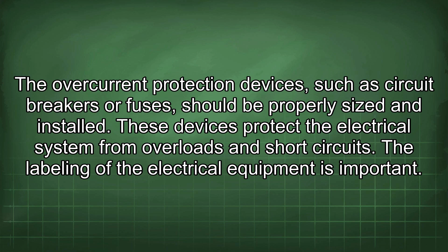The labeling of the electrical equipment is important. All electrical equipment, including meter centers, disconnects, and electrical panels should be properly labeled with clear and concise information. This helps ensure safety and facilitates maintenance and repairs. Consider future expansion when planning the electrical service. If there is a possibility of future expansion or increased electrical load, it is important to design the system to accommodate these changes. This may involve installing larger service conductors or providing additional capacity in the meter center.